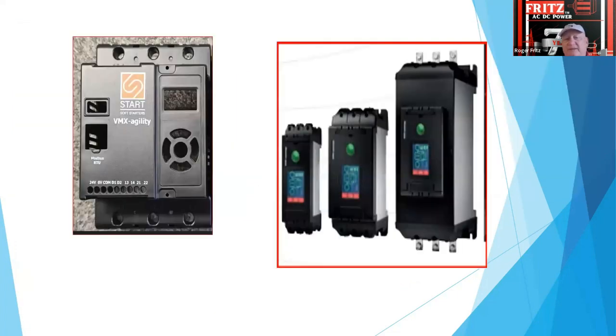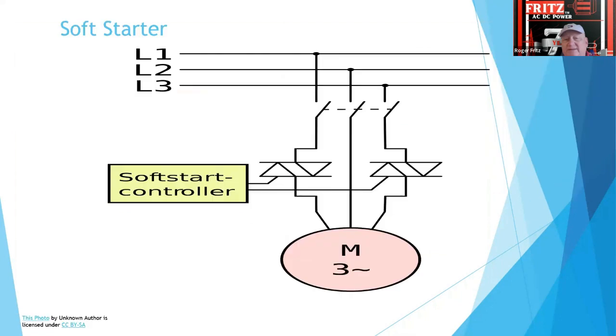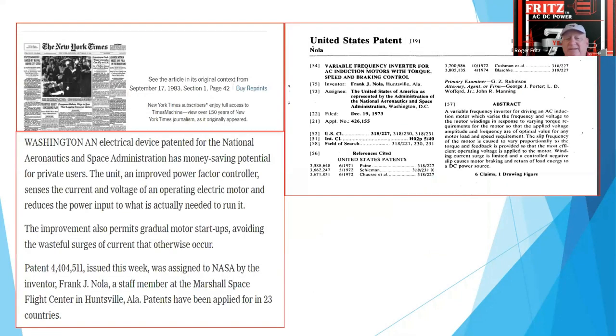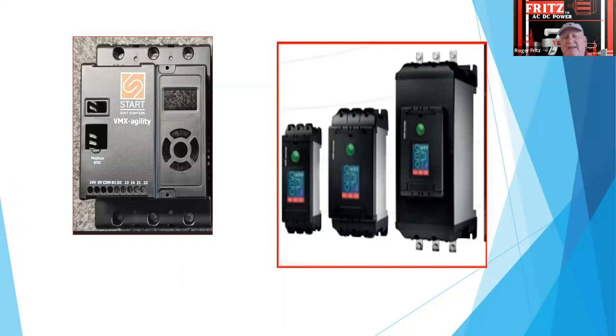There's a couple different types of soft starters. This is the type where it just soft starts it, and then it has a shunt inside that brings it all across the line again after it's running. The benefit is that you can regulate through the SCRs. You can regulate how much voltage and limit the current as you're bringing it up. So it's a wide variety of applications.